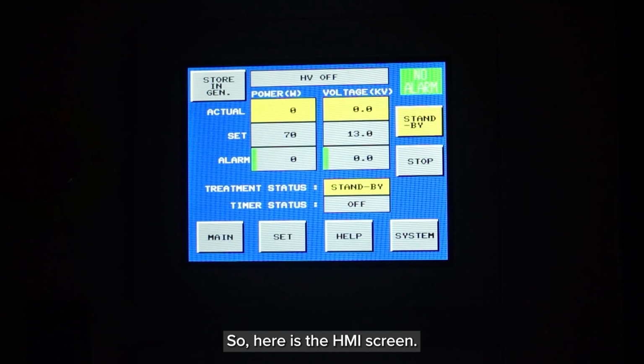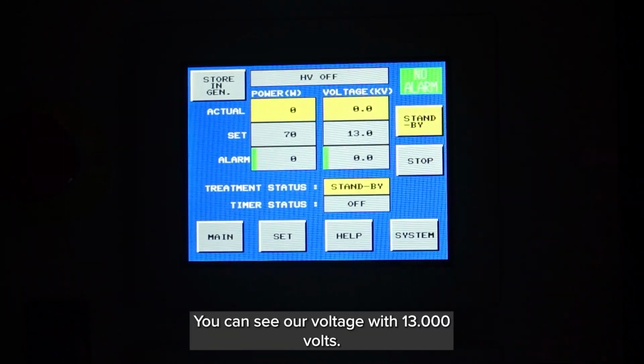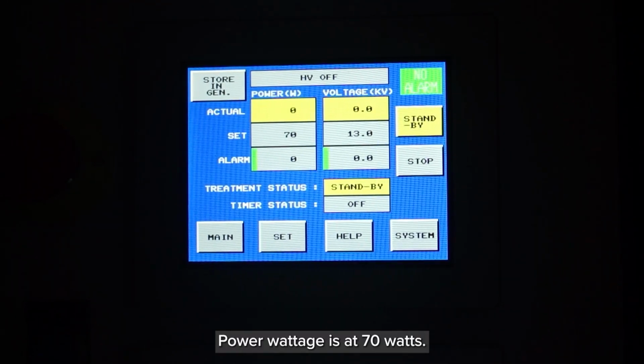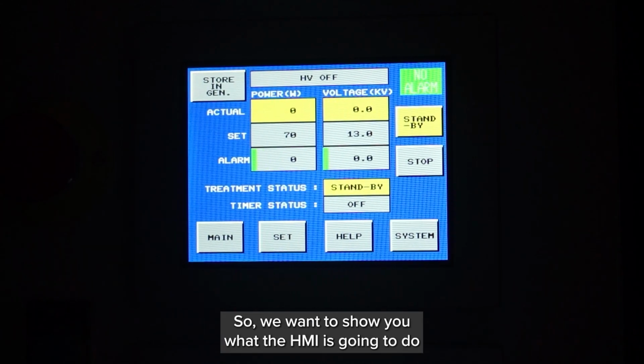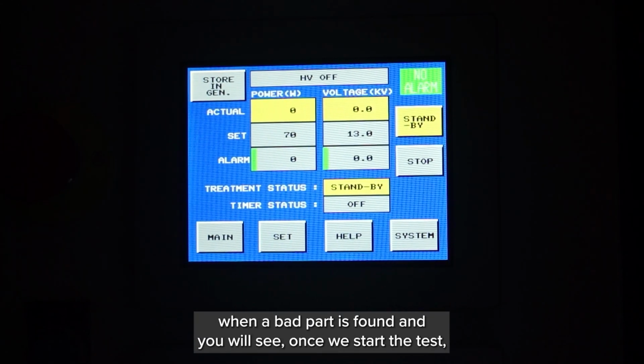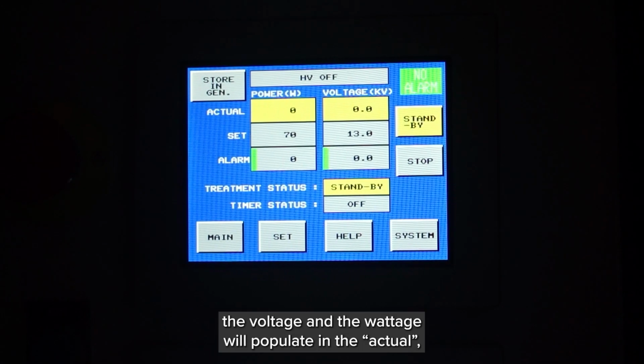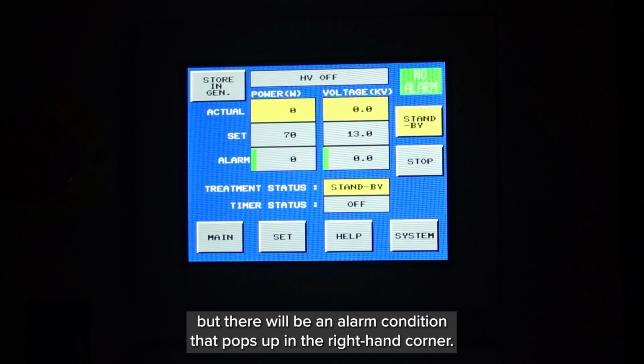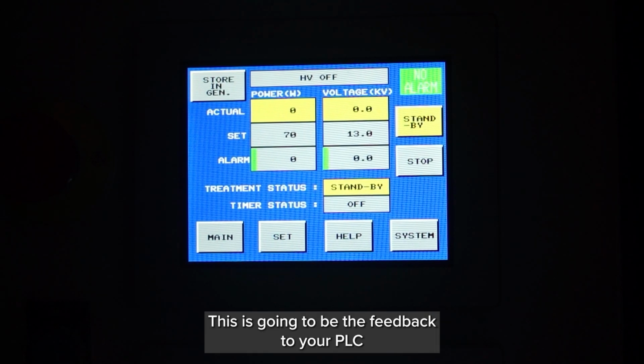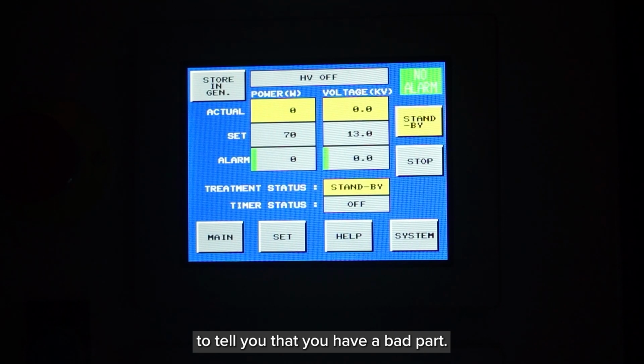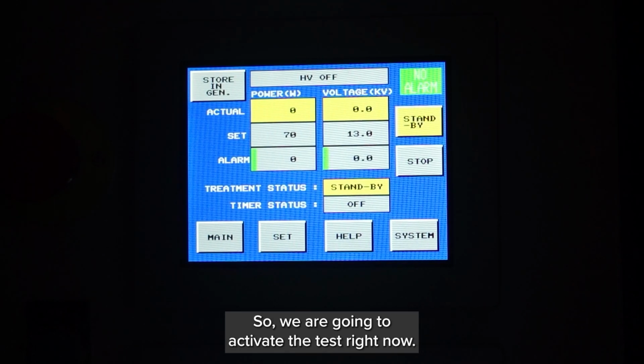So here's the HMI screen. You can see our voltage, which is 13,000 volts. Our wattage is at 70 watts. So we wanted to show you what the HMI is going to do when a bad part is found. And you'll see once we start the test, the voltage and the wattage will populate in the actual, but there will be an alarm condition that pops up in the right-hand corner. This is what's going to be your feedback to your PLC to tell you that you have a bad part. So we're going to activate the test right now.